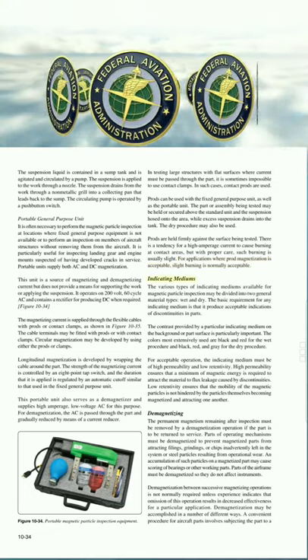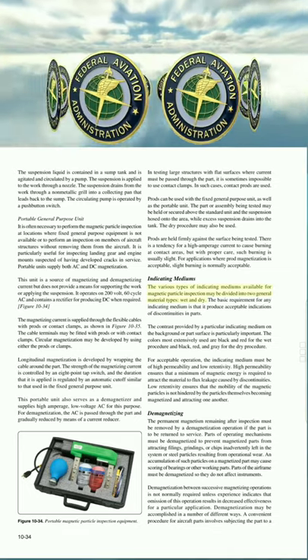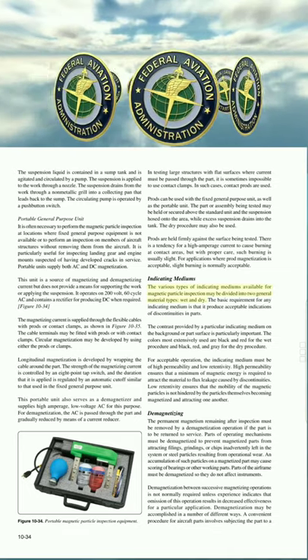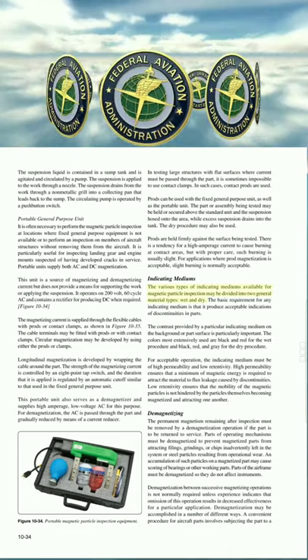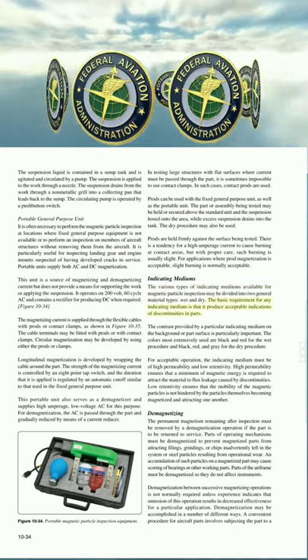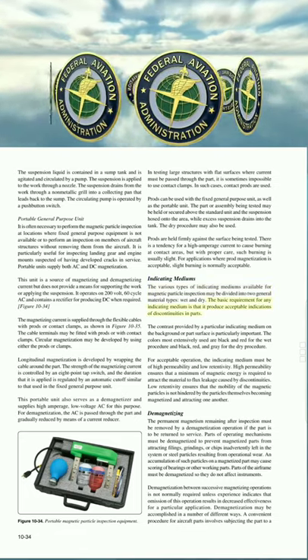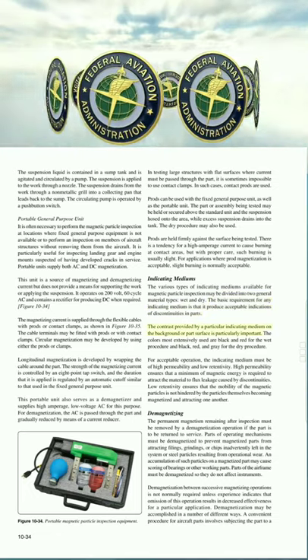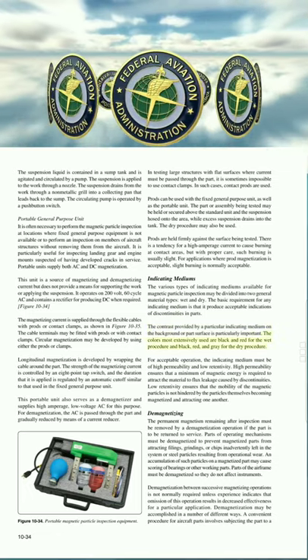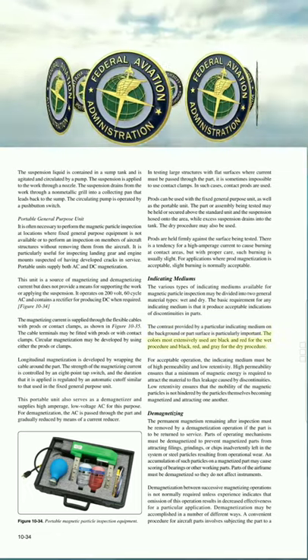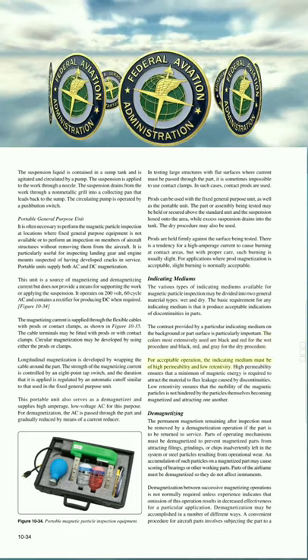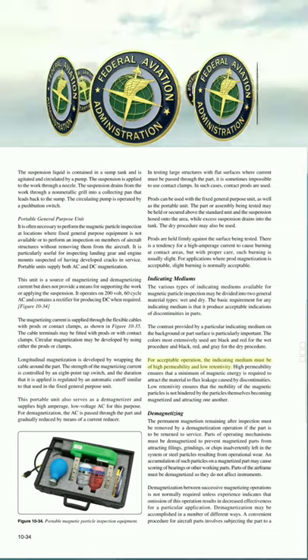Indicating mediums. The various types of indicating mediums available for magnetic particle inspection may be divided into two general material types, wet and dry. The basic requirement for any indicating medium is that it produce acceptable indications of discontinuities in parts. The contrast provided by a particular indicating medium on the background or part surface is particularly important. The colors most extensively used are black and red for the wet procedure and black, red, and gray for the dry procedure.